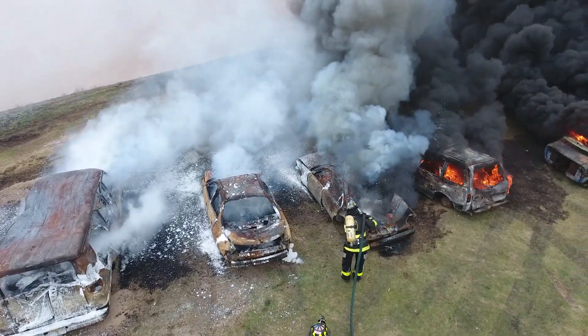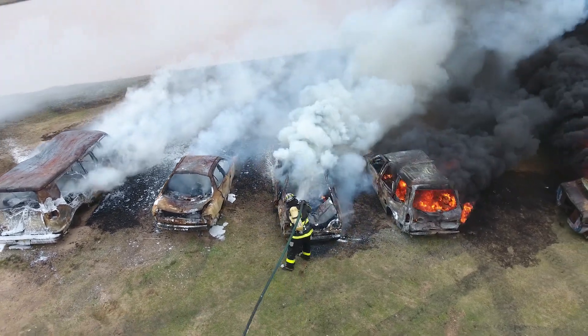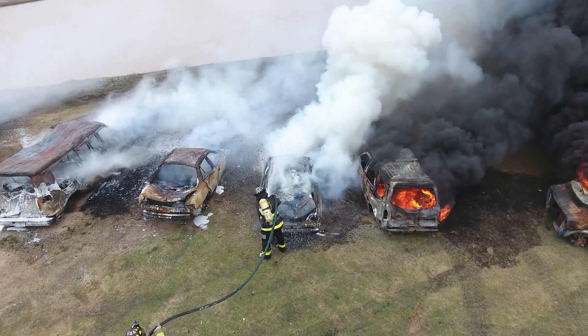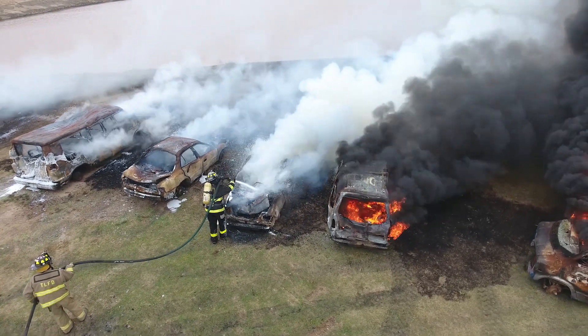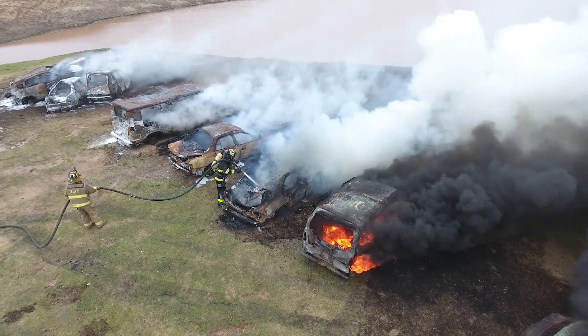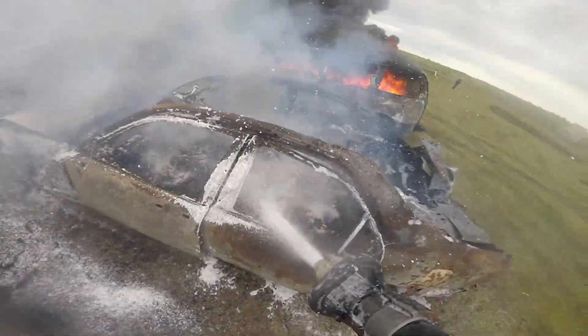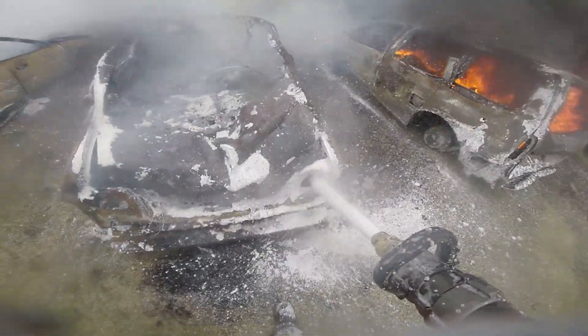CAFs is a huge leap forward for the rapid knockdown experience when applied to firefighting. CAFs became popular due to how efficiently it puts out fires with almost no extra damage caused by water and contaminated water runoff. This is possible because CAFs is attacking all three sides of the fire triangle: heat, oxygen, and fuel. Up to this point, firefighters have been concentrating solely on the heat, because water only attacks the heat side of the fire triangle. CAFs is also cutting off the oxygen to the fire by surrounding the fuel in a foam barrier, thus preventing further toxins from being released into the atmosphere.